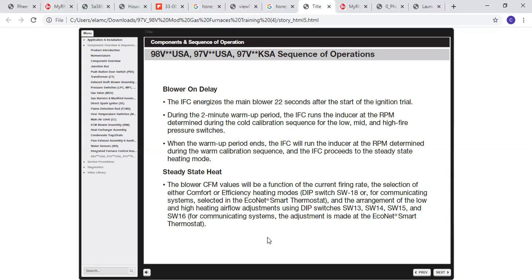If you're in steady state heat mode, the blower CFM values will be a function of the current firing rate. The selection of this is either in comfort or efficiency modes, using dip switch SW18, or if you're using a communicating EcoNet, that can also be set up in the EcoNet thermostat as well.